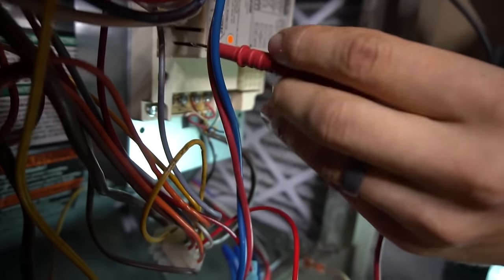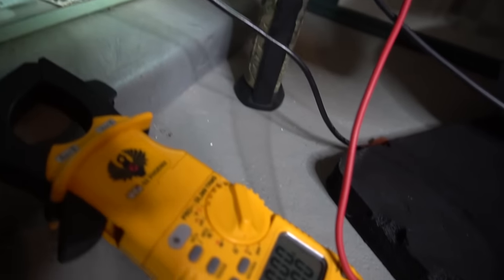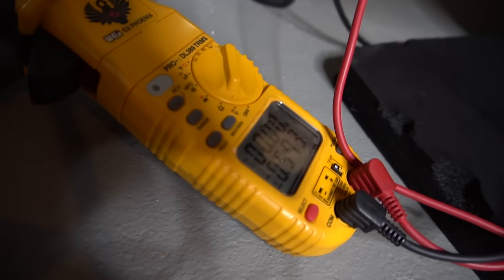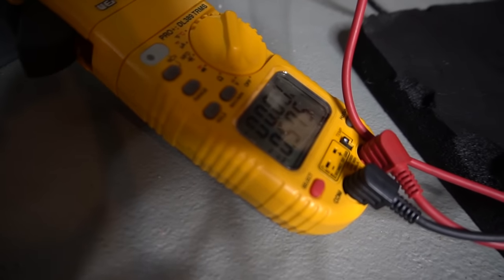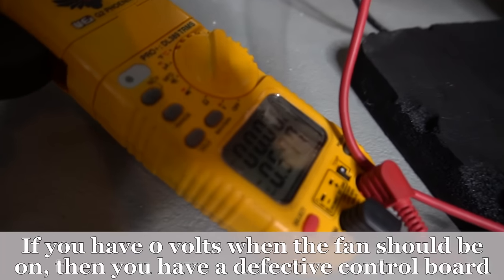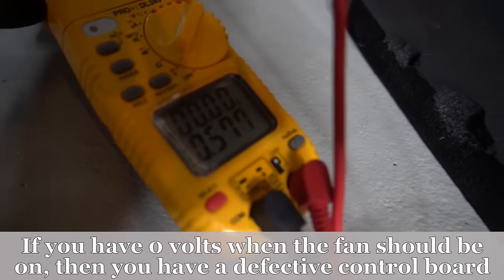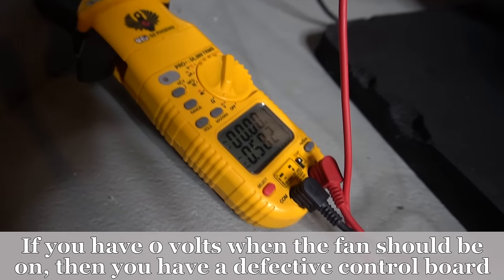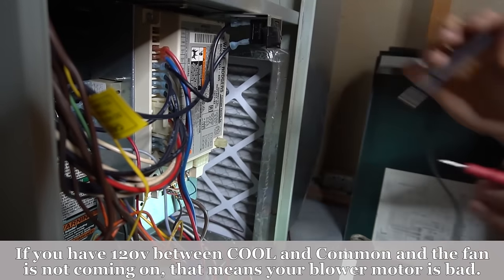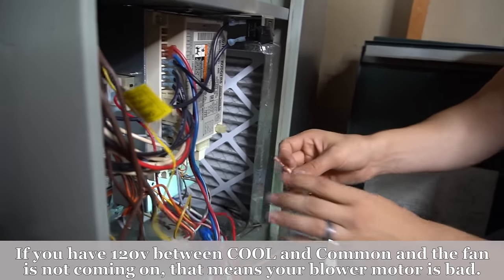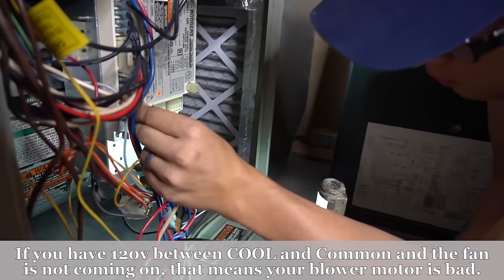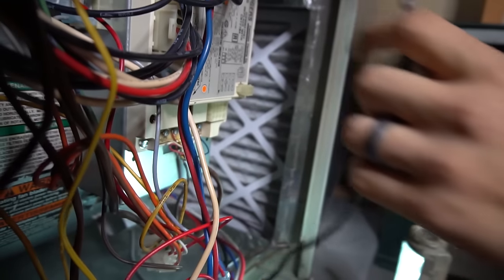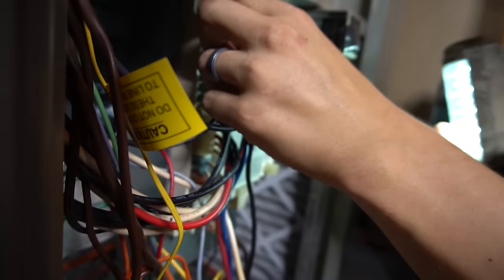And when you check that, if your motor is getting power, it'll have 120 volts. If you're not getting voltage, that means actually your control board is simply not sending power to the blower motor. And it's probably the board that's bad and not the motor itself. But if the board is sending 120 volts to the blower motor, that means the blower motor is bad if it's not turning on. And then don't forget to plug the wires back in.